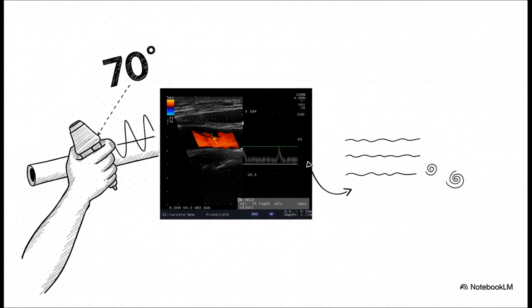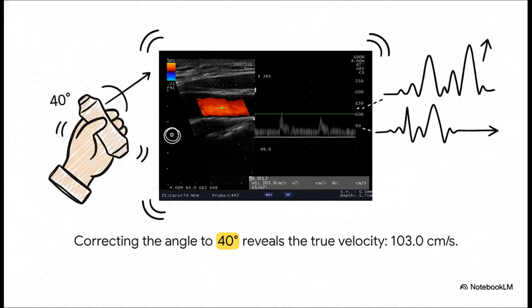Okay, let's make this real. Look at this example. The operator here has a really bad angle, 70 degrees, way over that 60-degree limit. And what does the machine say? It clocks the blood speed at just under 36 centimeters per second. Okay, remember that number. Now watch this. This is the aha moment. The clinician doesn't change anything else. They just adjust the probe a little, get a much better angle. Now it's 40 degrees. And bam! Look at the new measurement, 103 centimeters per second. That is 3 times faster than the first reading. It's the exact same blood flowing through the exact same vessel. The only thing that changed was the angle. And that shows you how one measurement was completely wrong and one is telling the truth.